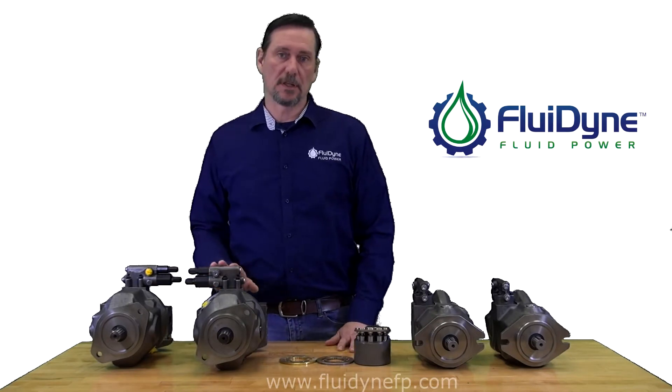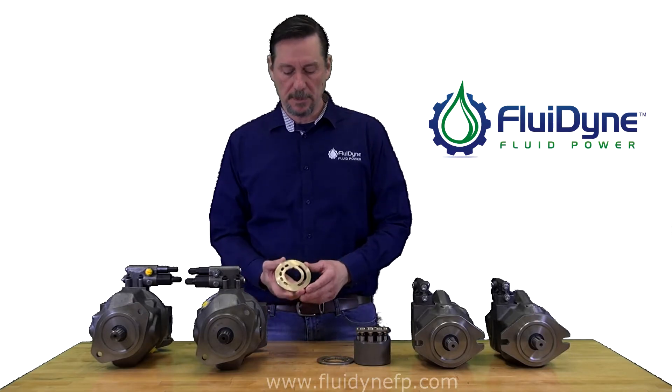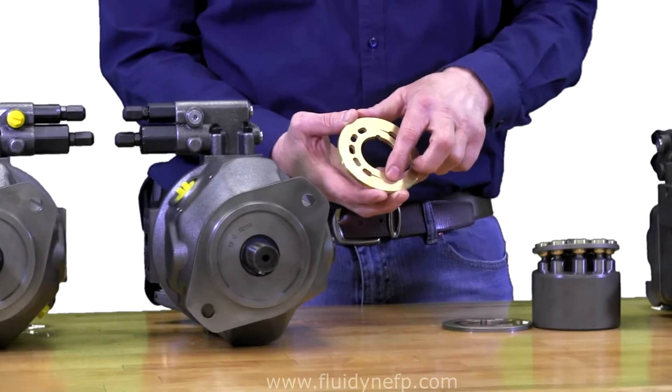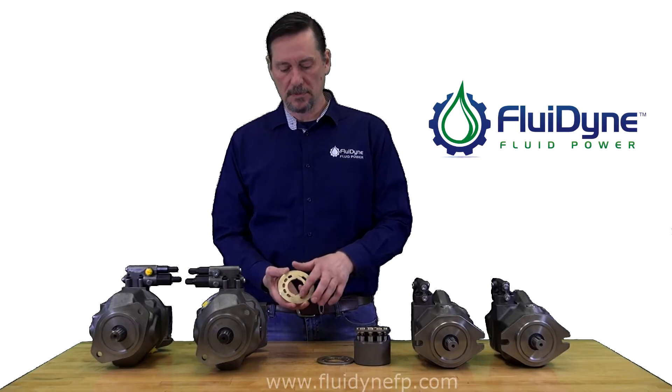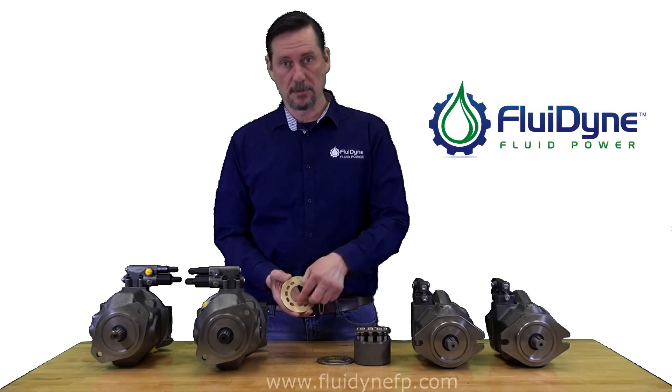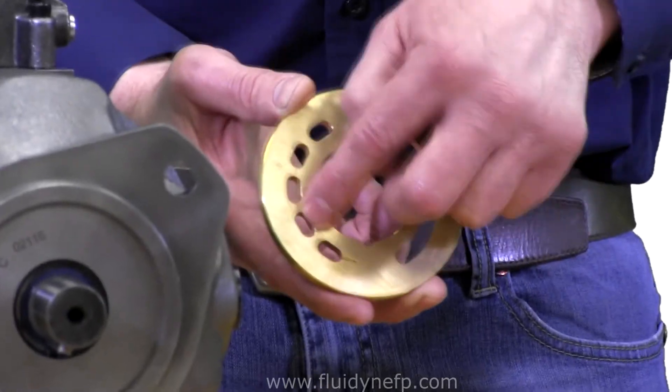Now if for some reason the compensator is gone or you receive the unit taken apart, there are other ways to determine rotation. You can check the valve plate. The valve plate always has decompression grooves and compression grooves. Depending on which way they're pointing, that's going to determine rotation. This one in particular is right-handed — it narrows down to a point but then opens up towards the right-hand side. So that's right-hand rotation.